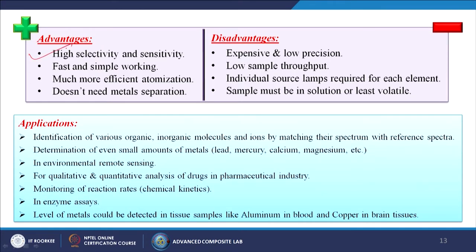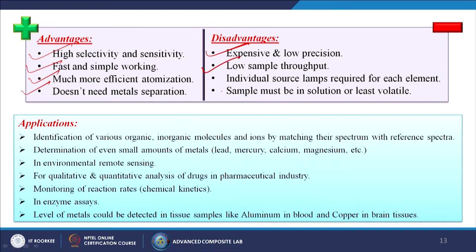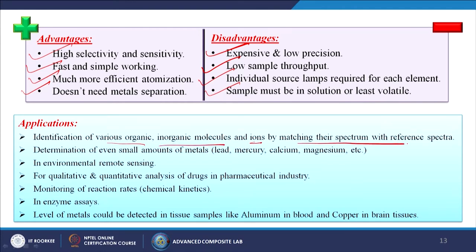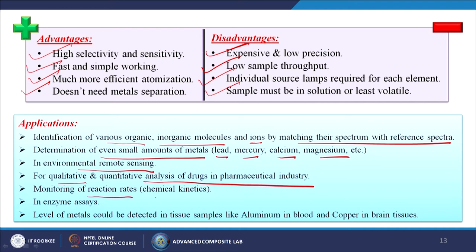Advantages of AAS: high selectivity and sensitivity, fast and simple working, much more efficient atomization, does not need metal separations. Disadvantages: expensive and low precision, low sample throughput, individual source lamps required for each element, and sample must be in solution or at least volatile. Applications: identification of various organic and inorganic molecules and ions by matching their spectrum with reference spectrum; determination of even small amounts of metals like lead, mercury, calcium, magnesium in environmental remote sensing; quantitative and qualitative analysis of drugs in the pharmaceutical industry; monitoring of reaction rates in enzyme assays; detection of metals in tissue samples like aluminium in blood and copper in brain tissues.